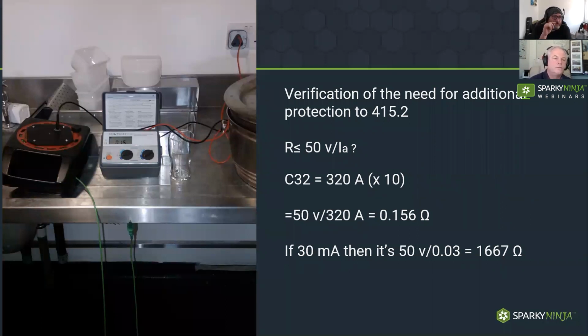So I carried out this test. This is a continuity test from the R2 of the CPC of the socket outlet to the metalwork of the sink, the readily accessible metalwork, not looking for the closest point of earth, but a piece that the user of that location can touch.